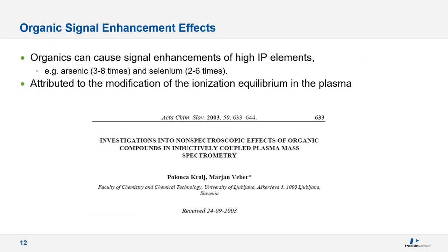Another approach for labs analyzing EPA Method 200.8 to achieve lower detection limits needed for arsenic and selenium is the addition of organics. In the presence of a small amount of organic, the ionization equilibrium within the plasma for these higher ionization potential elements can provide signal enhancement. Many labs add a small amount of methanol or isopropanol to their internal standard mix to help provide this improvement to their signal. The paper shown here discusses the causes and extent of those signal enhancement effects.